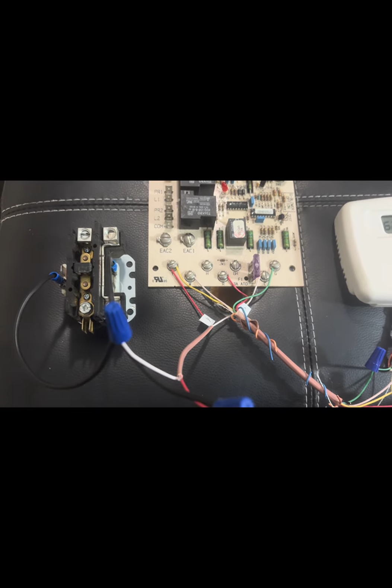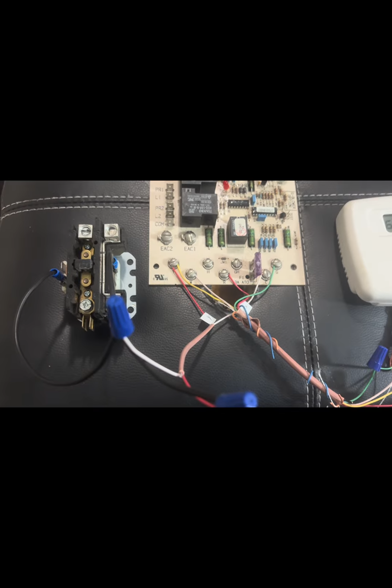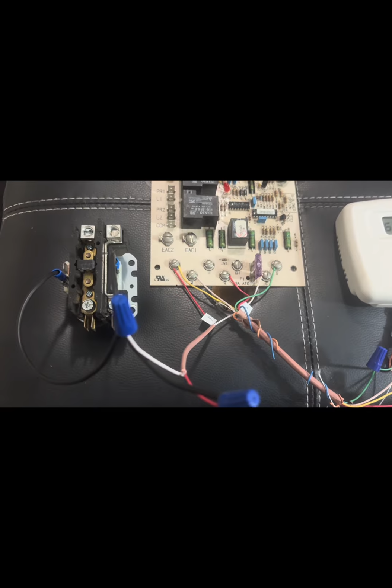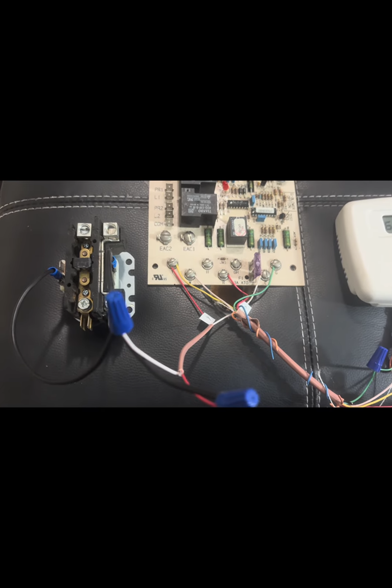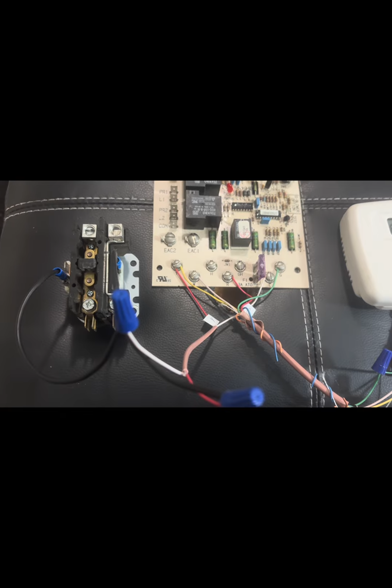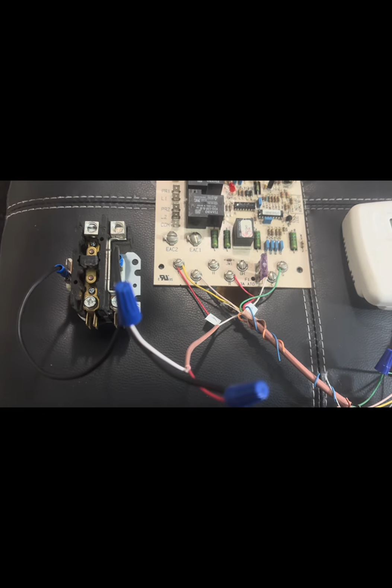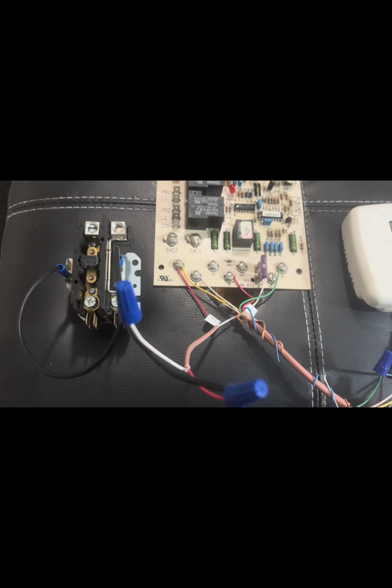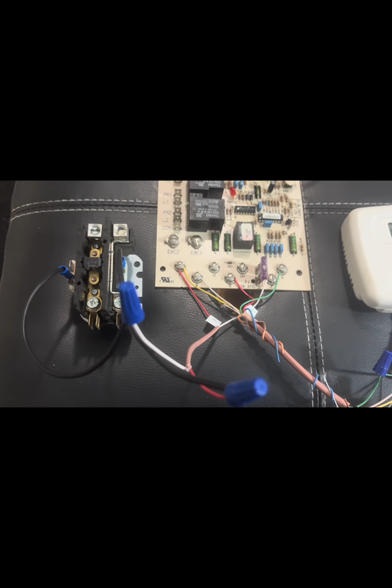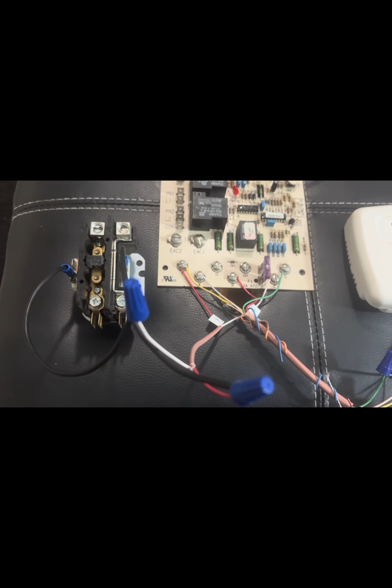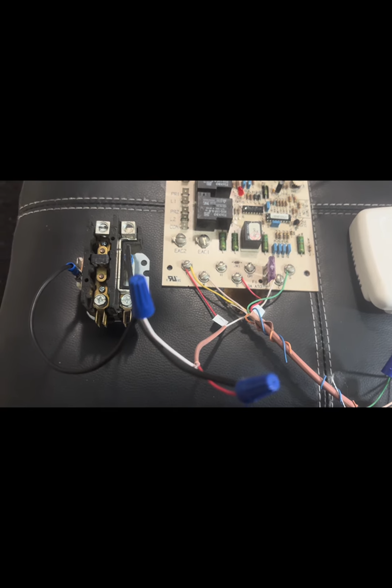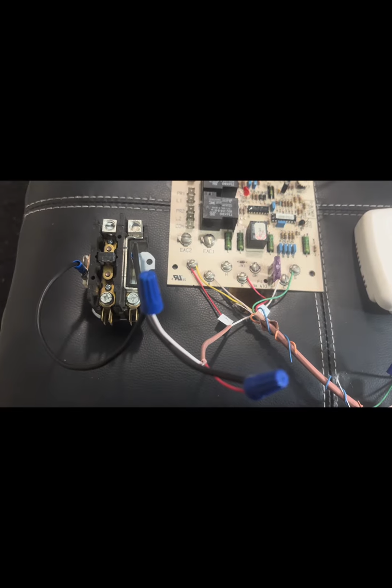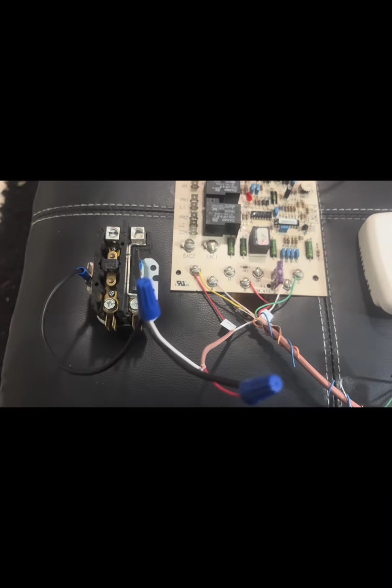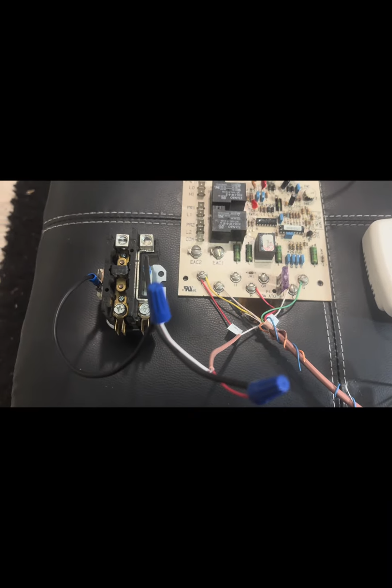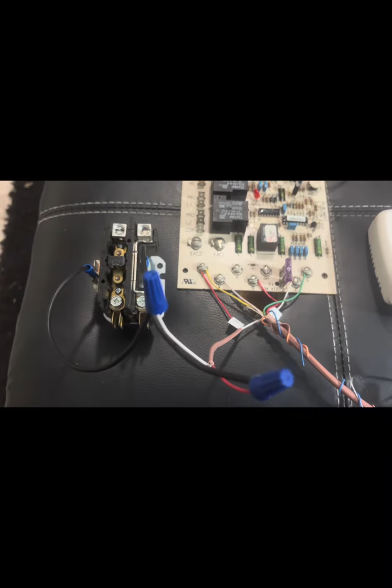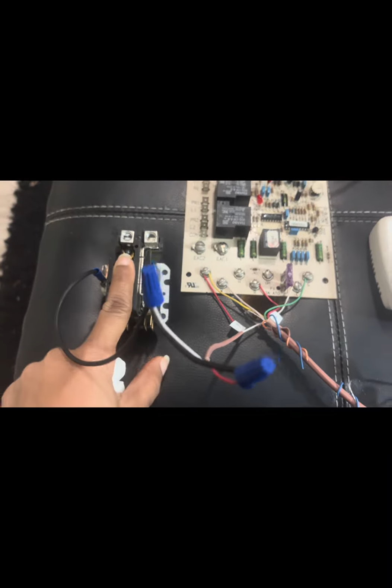The 2 low voltage wires coming from a straight cool condenser are your Y and your C. Sometimes it can be yellow and blue. For this example, I'm going to use white and red. That's kind of common. So we know the Y calls signal for cooling, the C is the power return path. The C will be your common, and the Y can either be a yellow, pink, purple, whatever color you want it to be, but that'll be the one that's going to energize the call for cooling.